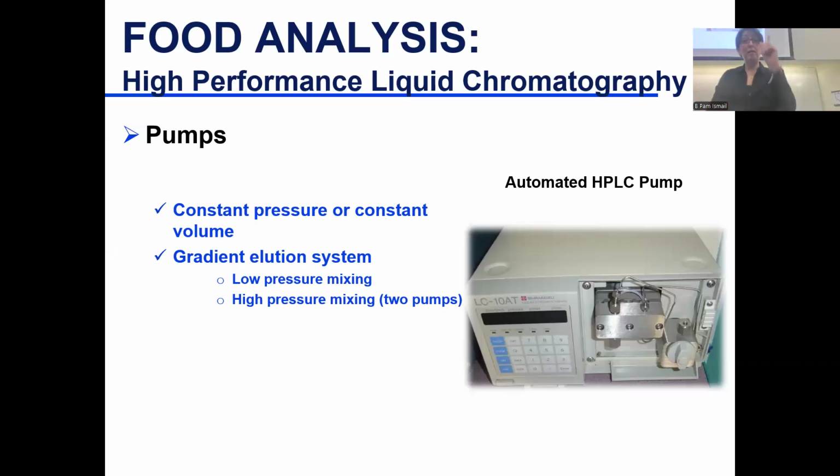Some systems have one pump and like 4 different mobile phases. These can get mixed under low pressure before entering the pump, and then the pump pumps them into the injector. You still get good mixing, but probably not as efficient as high pressure mixing.